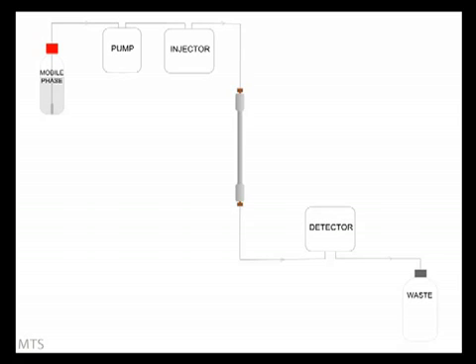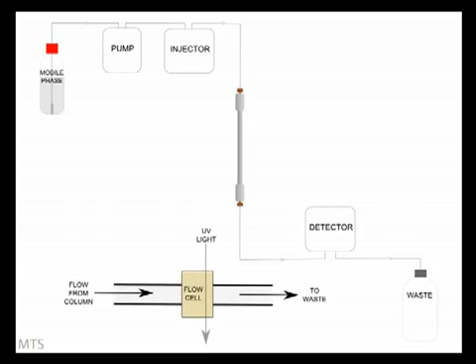The detector is designed to be able to recognize some characteristic of the sample component. The most common detector is probably an ultraviolet or UV detector. This works by passing a beam of UV light through the flow path of the mobile phase, measuring the absorbance. For those components which absorb UV light, the response obtained will be proportional to the amount of the component present. Not all components absorb UV light and those that do have different responses, so these factors need to be considered when choosing a suitable detector.